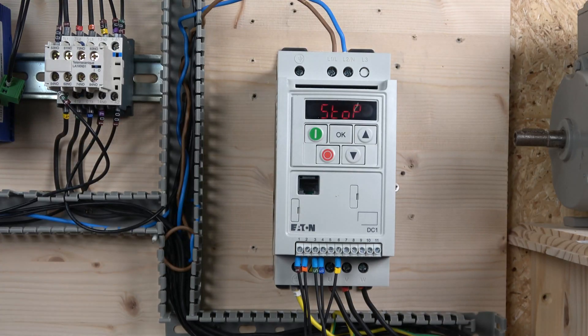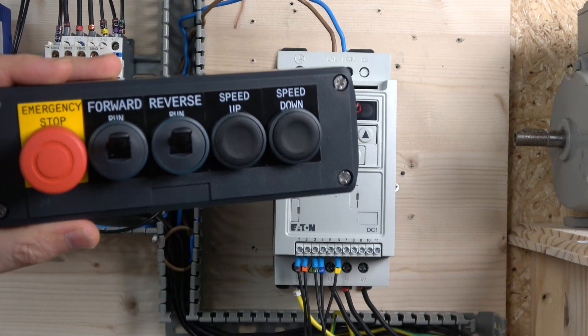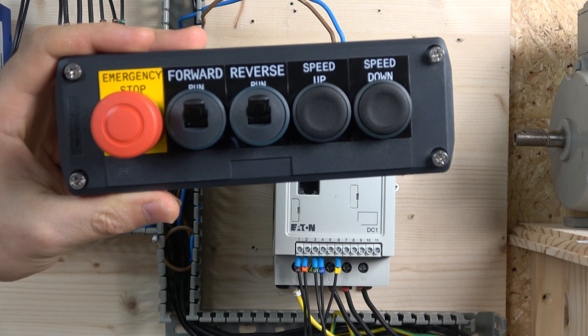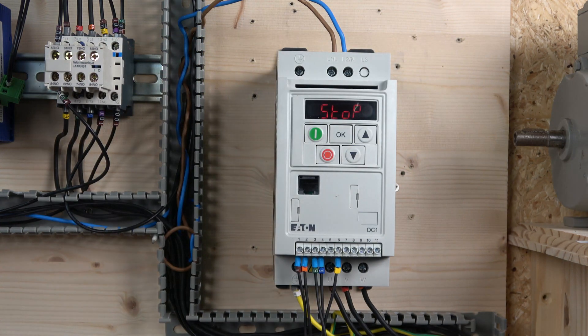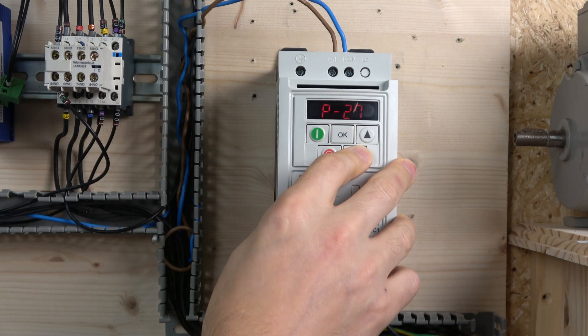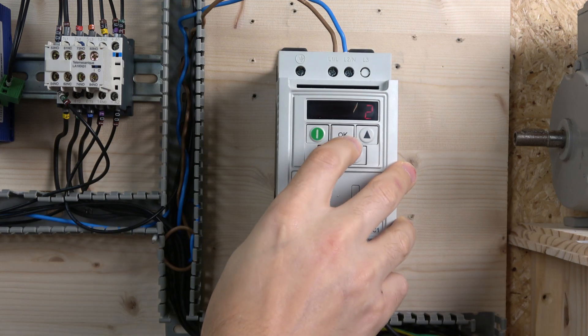Here we go ladies and gentlemen. The first setup we're going to be using in this video is the two up-and-down button speed control. The station is going to look more or less like this — we'll have a forward run, reverse run, and then we're going to use up and down buttons to change the speeds. For that we need to change some parameters. The first one is to make sure that parameter 21 is set to 2.